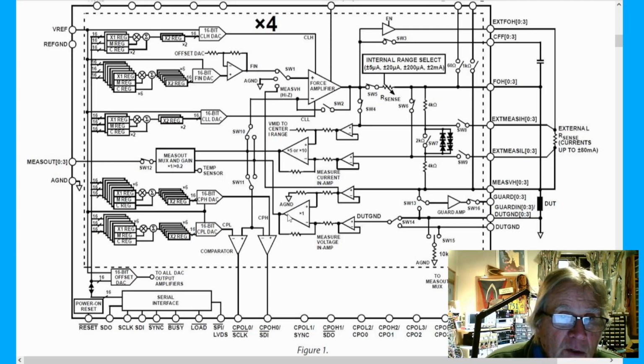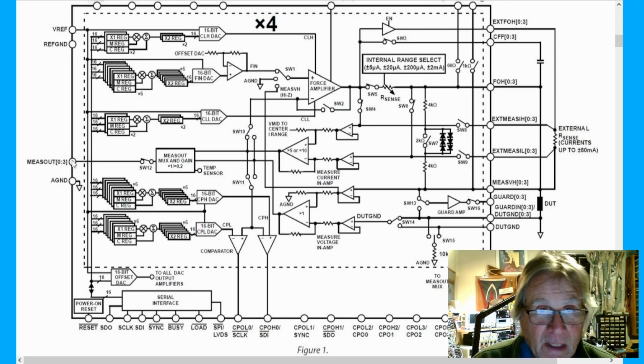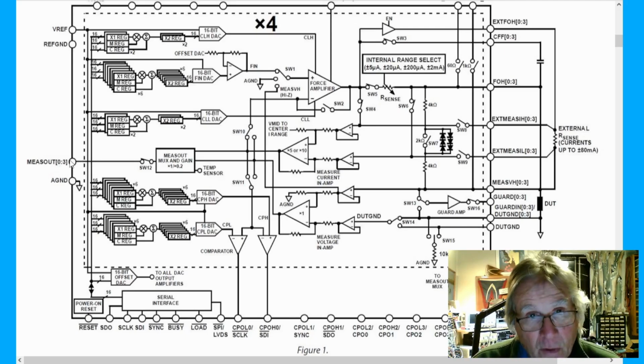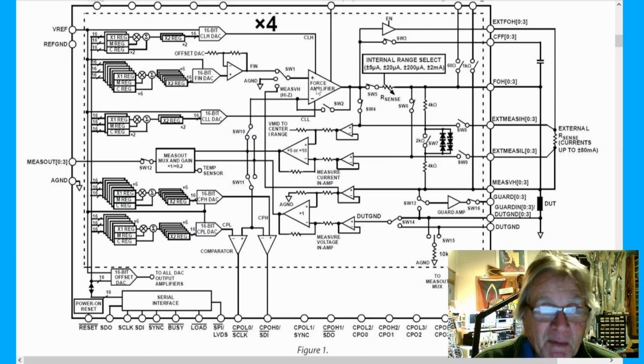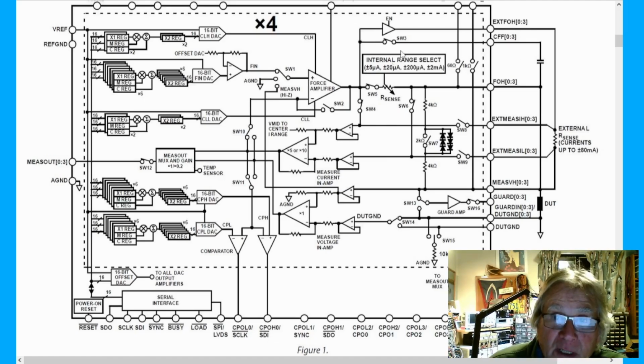In addition, the 2 measure amplifiers go into this multiplexer, the measure output mux and gain, and through an enable switch to make the measure output signal. And the measure output signal is used to drive the A to D converter, which measures either the voltage or the current. Typically you will force voltage measure current, or you will force current measure voltage, although you can measure both. So we covered most of the analog circuitry here.